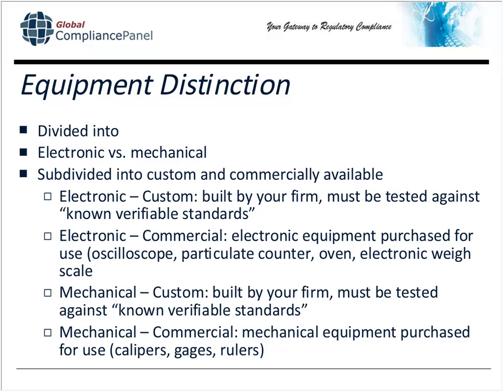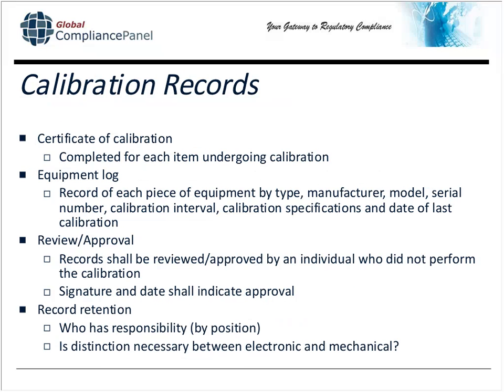These are the ones that you can calibrate in-house against the commercially available standards: the calipers, the gauges, the rulers, things like that. You've got to have documents that evidence the calibration. It's not just enough to have a sticker on your piece of equipment. I've seen them called certificates of calibration in the past, and you've got to have that for each item that undergoes calibration.